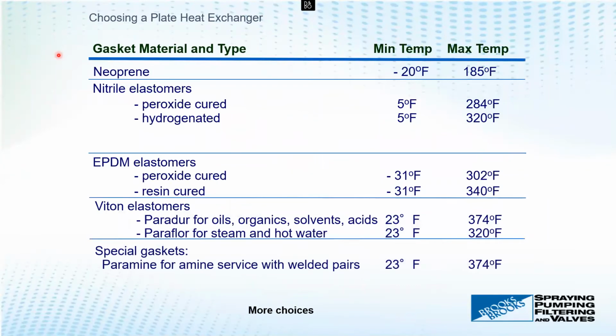Here's a more explicit look at the temperatures that gaskets can hold. Very common gasket materials for all plate and frame manufacturers include the rubbers — Vitons, nitriles, neoprenes, EPDM — and then special gaskets. Paramine is an interesting one, certainly for the Alberta folks, but anywhere there's amine service, paramine is the gasket we've found the most success with, usually used with a welded plate pair.